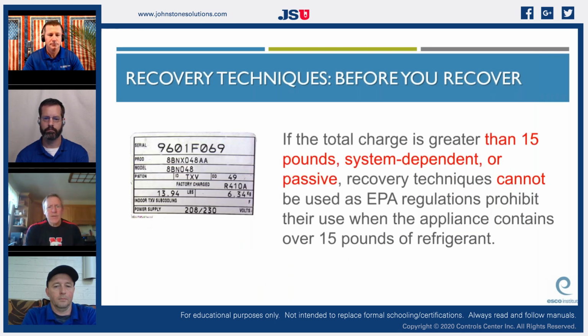So if the nameplate reads more than 15 pounds, it cannot be a system-dependent recovery process. You can't use the compressor in a system to recover it without a recovery machine if it's over 15 pounds. This particular one's 13.94, so you could use it. I think we covered that early, probably in the core somewhere. Yeah, and a little bit in Type 1.